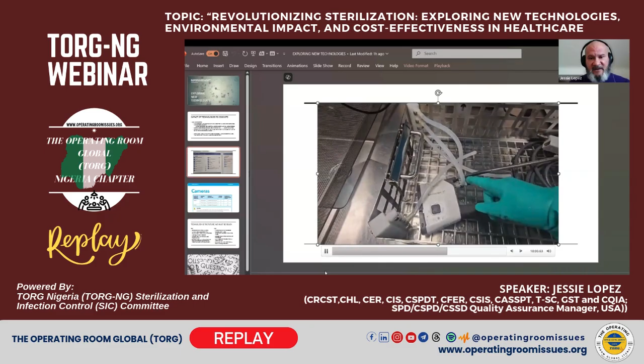And again, this video here is going to be a little bit over 20 something minutes. This is just showing you the tip. It's not showing you what I did to prepare the device before. It's not including the 30 minutes of soak time, and it's not including the time it takes to ultrasonic. Ultrasonicking alone requires 15 minutes of active ultrasonicking. Because this does irrigation and rinsing and thermal disinfection, this actual process takes about 45 minutes. 45 minutes, 30 minutes of soaking for the manual cleaning. That's over an hour of dealing with one device.